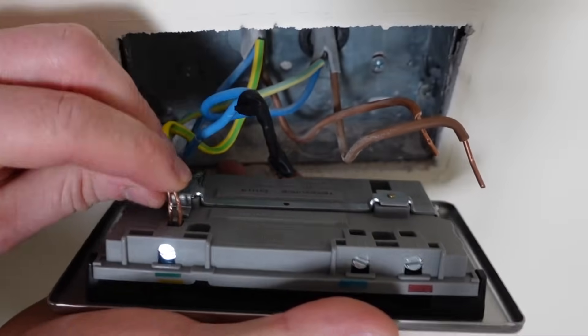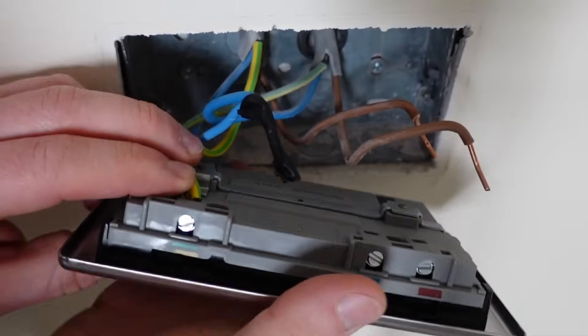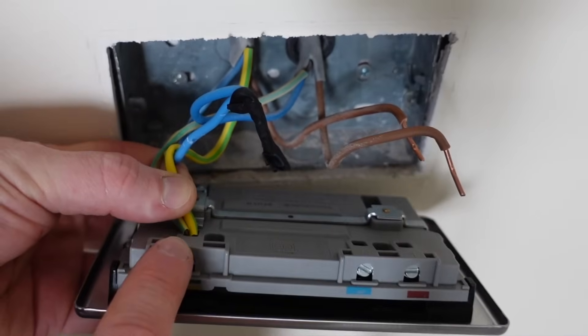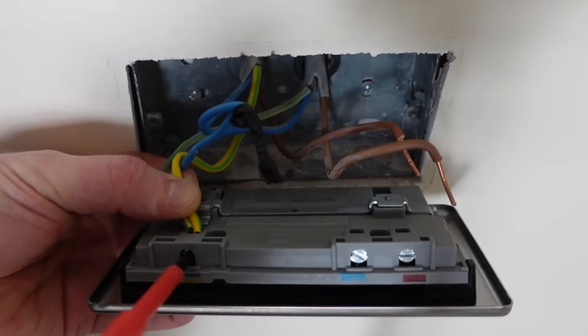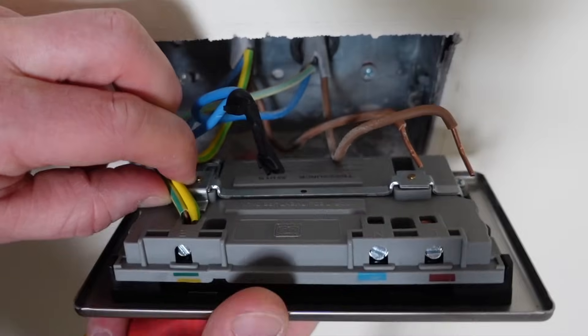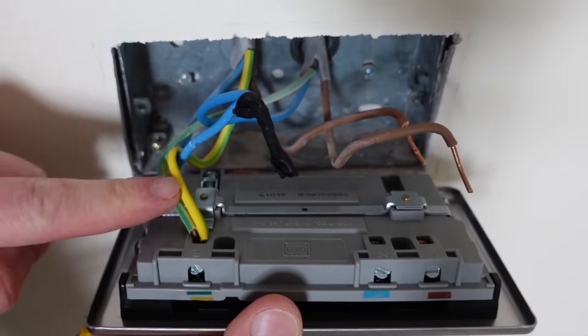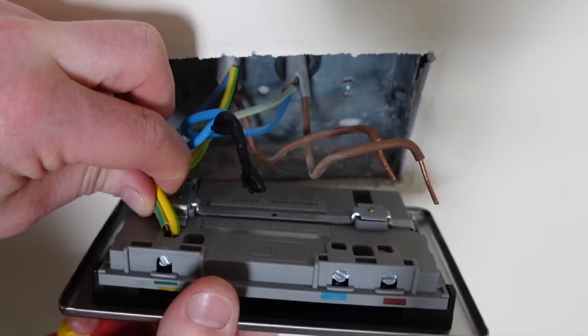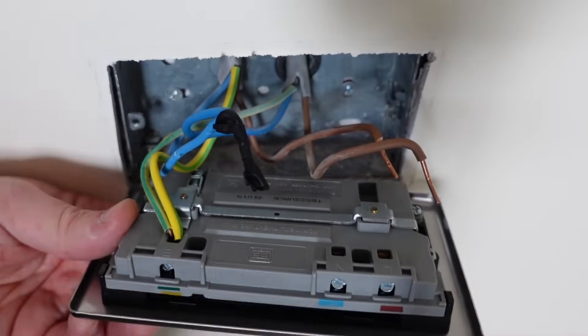So we'll pop the earth wires into the earth terminal, both of them, and just make sure that you have no exposed copper. And then we'll do up that earth terminal nice and tight with our screwdriver and just give them a little tug because sometimes especially when we've got two wires in each terminal you don't get good contact and a wire could pop out. So make sure you give them a little tug.